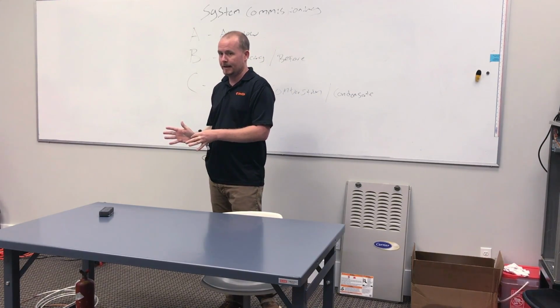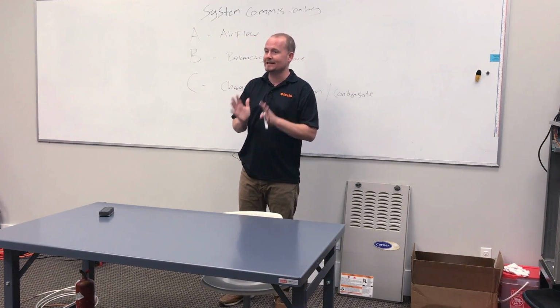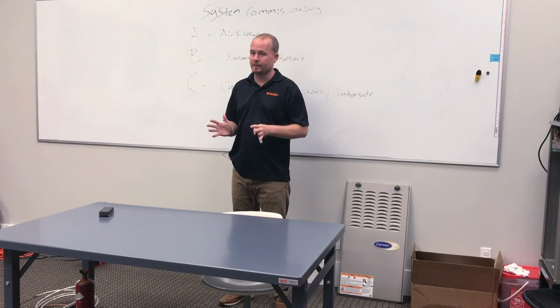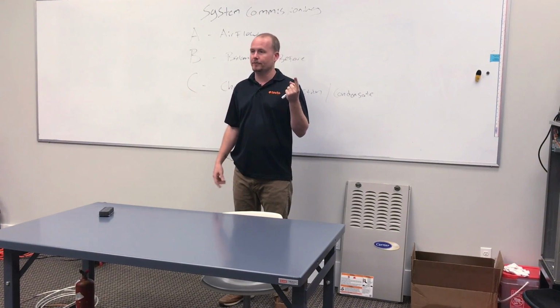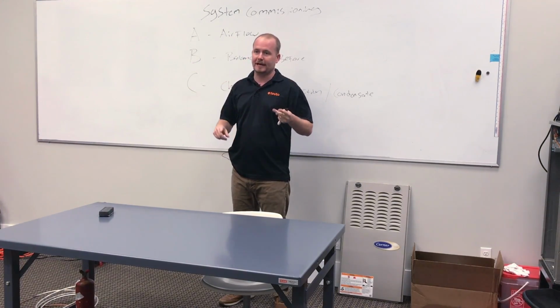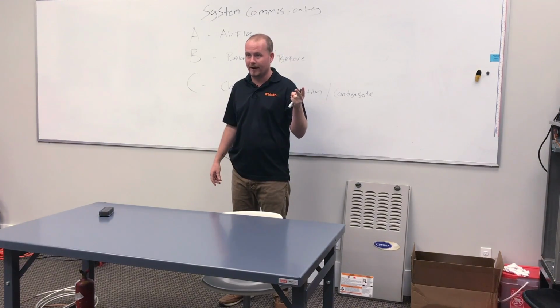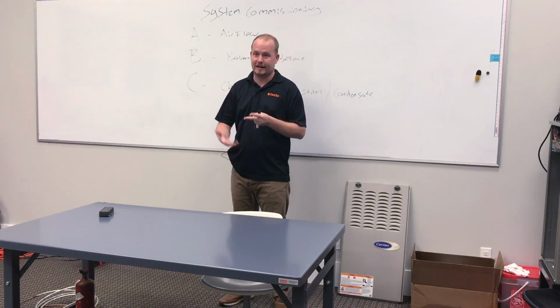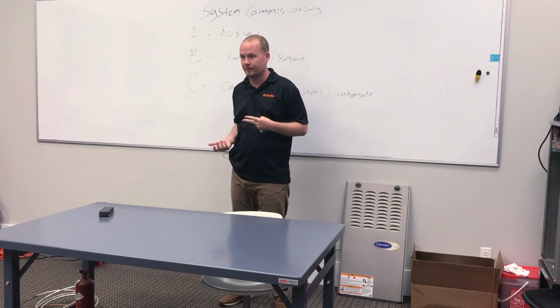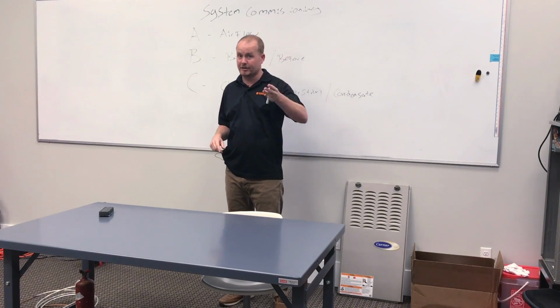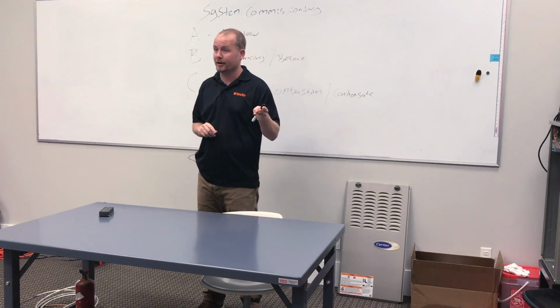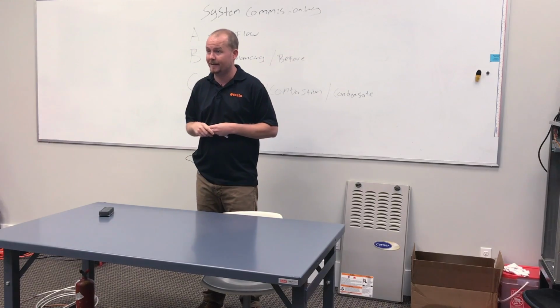Does that make sense? And so on new equipment, it's much easier, because you've got a brand spanking new piece of equipment. You've got a nice fancy chart that you can reference right away if you want, right there on your phone, because it's Carrier. You've got the Carrier app. You can reference that chart if you want. If you set it up properly, it's pretty much always going to be 350 per ton, so you really don't even have to do anything more complicated than that.